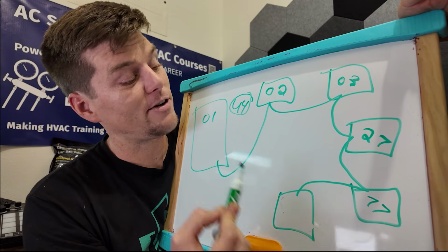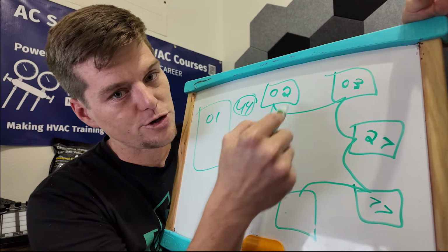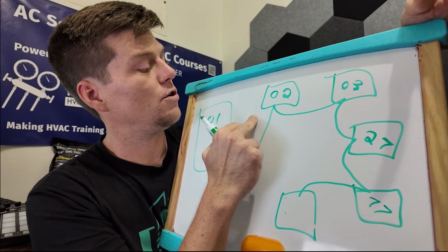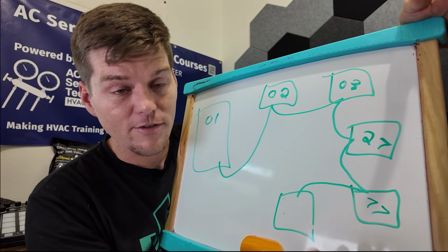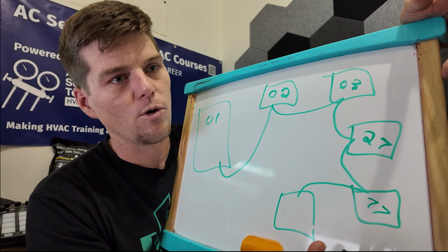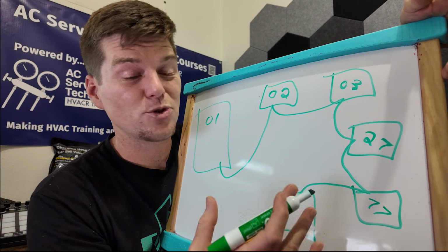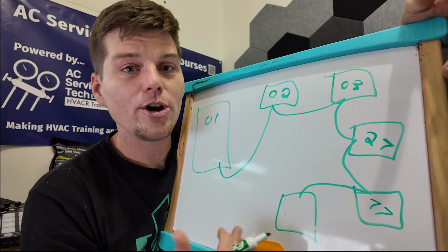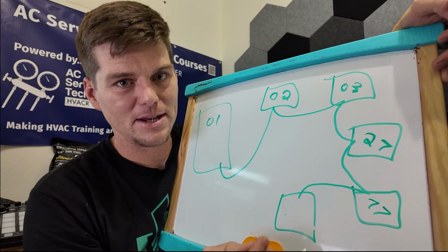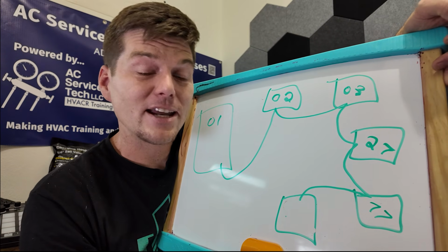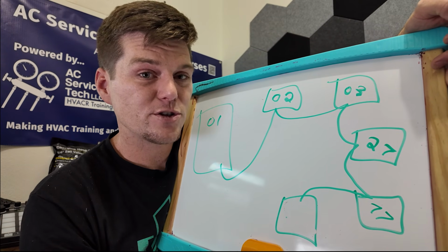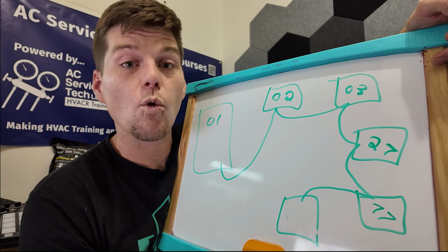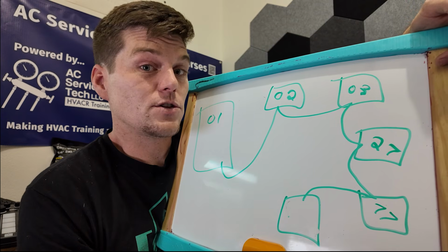Once we've done that and we verify there's power here, now we can start troubleshooting the communication network to see what's happened. Because we can't see that all from one place. You can either hook up your service tool and see how many indoor units you have. But again, if you have a communication fault like U4, hooking up Service Checker or a service device is almost a waste of time. Because we know that if the communication doesn't work because it says it doesn't work, hooking up to it and trying to look at it with a service tool doesn't mean it's going to fix the problem. It just means that it's not going to populate. And you're going to spend a ton of time hooking up a service tool that isn't going to fix the issue. The issue is it can't see somebody, right? It can't see somebody that it once saw, or it's not communicating the way it needs to.